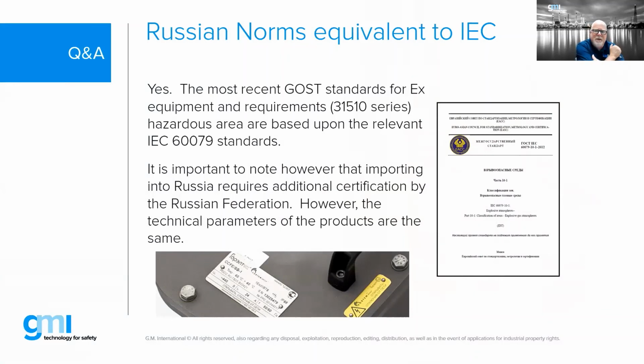You have to pay for them and all that, but they are based upon the relevant 60079 standards. The important thing to note, and you might be able to see a bit of that label in the bottom picture, is that the markings are not just your normal markings you'd find. There are additional markings, and it also has to be in Russian. But the actual performance of the product, if you build it to an IEC or EN standard, getting Russian approvals is typically more of a transactional cost and maybe some label changing, but that's basically the main issue: the performance.